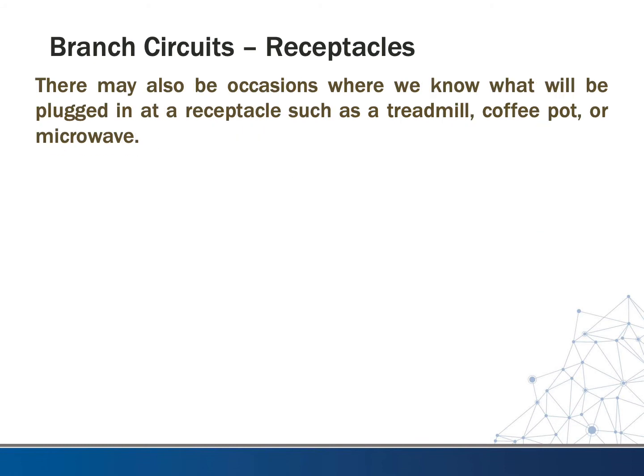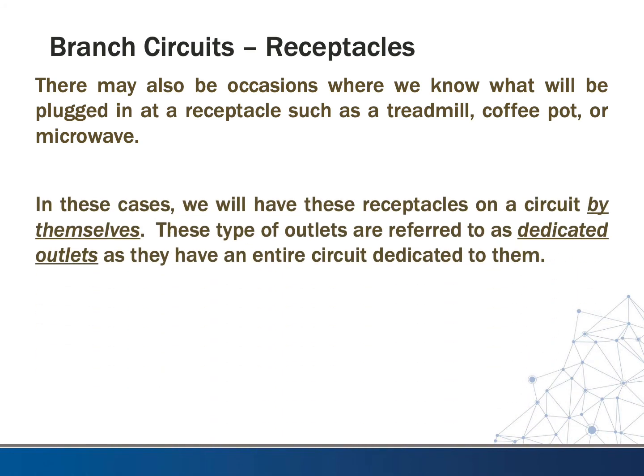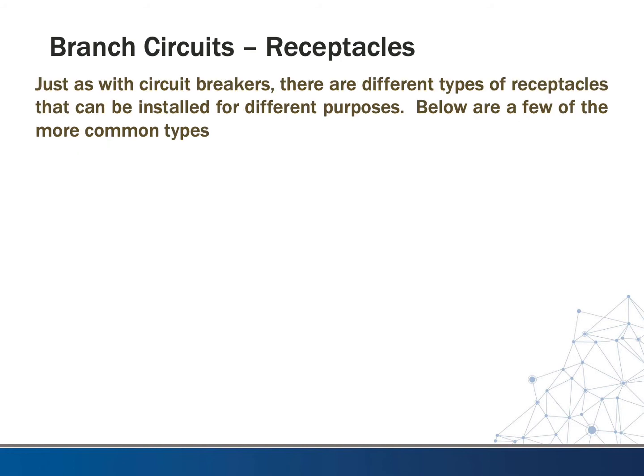There may also be occasions where we know what will be plugged in at a receptacle, such as a treadmill, a coffee pot, or a microwave. If you have enough information from the architect or owner, they may actually locate these on the floor plan. In these cases, we will have the receptacles on a circuit by themselves for these larger loads. These types of outlets are referred to as dedicated outlets, as they have an entire circuit dedicated to them.